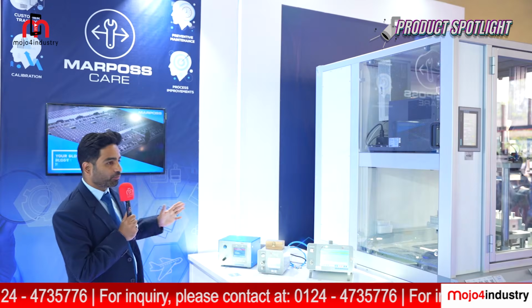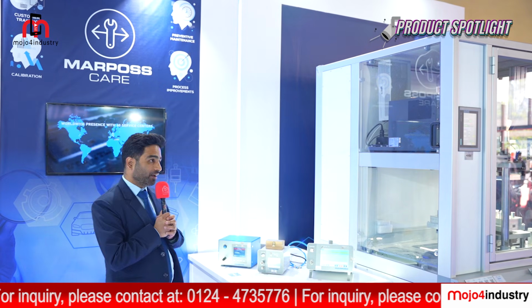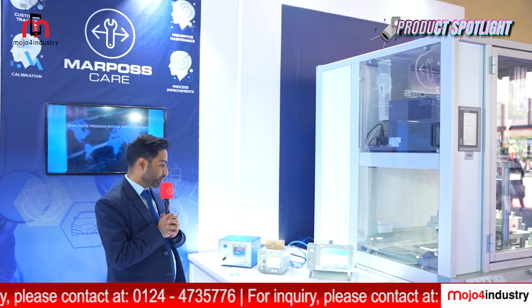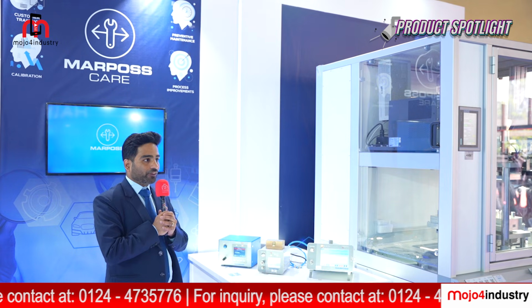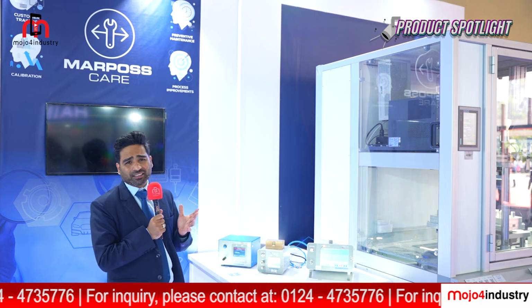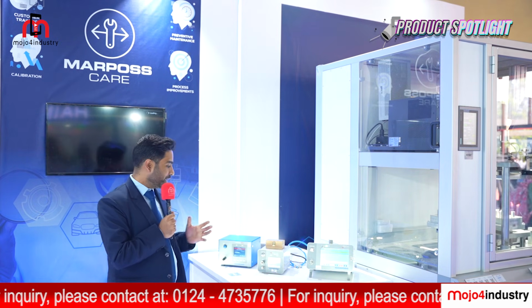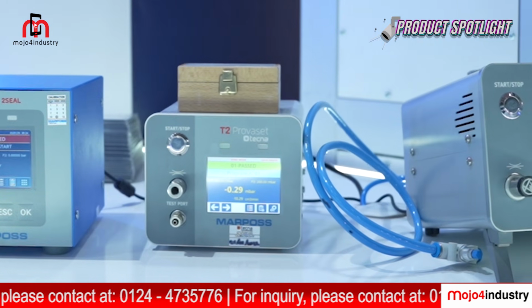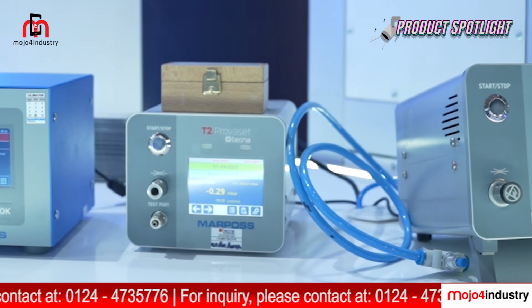The first solution here for the biomedical industry is leakage testing of any kind of disposables. If you have disposables like urine bags, blood tubings, catheters, and you want to conduct leakage testing, you can easily conduct that through this particular device. We are able to conduct the leak testing through the pressure difference method as well as the flow method.